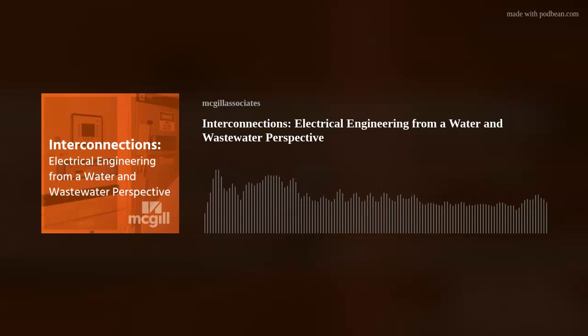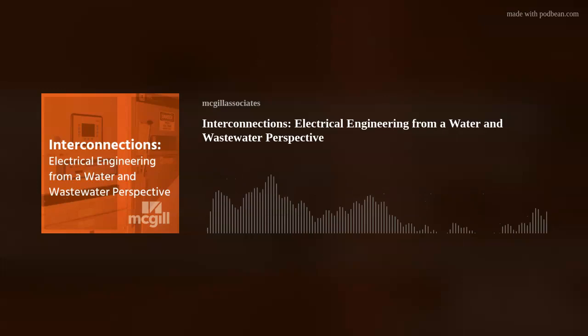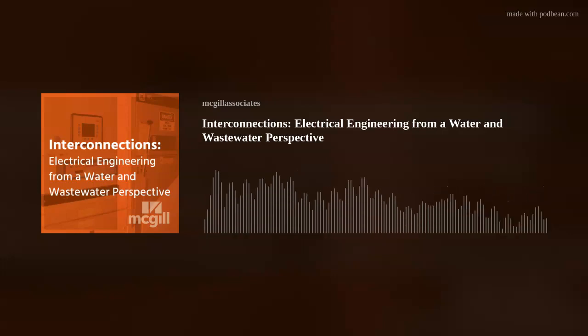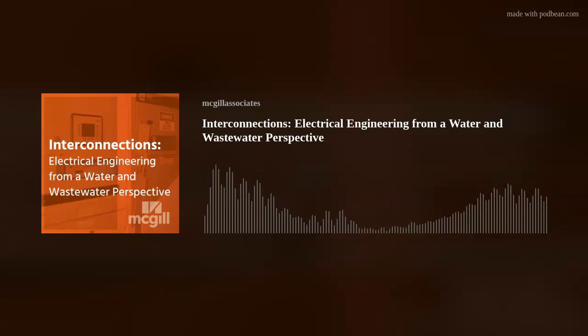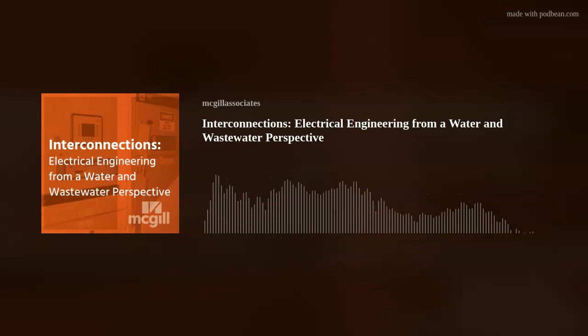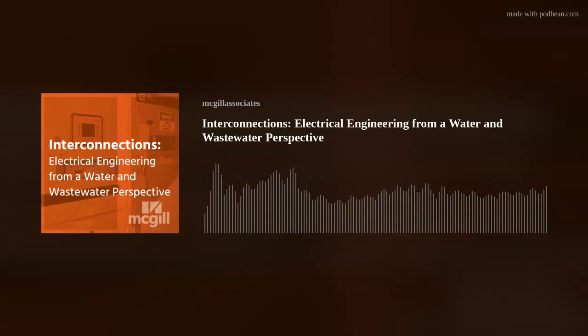And then with warnings and things like that, you might be able to see trends. Part of the SCADA system, you've got a historian in there, so you can watch and monitor certain things. You can monitor levels in tanks, you can monitor run hours on pumps. Am I having to run my pumps longer to get a certain height in the tank? Does that mean my impeller or my pump is getting bad or wearing out? Things like that you can catch through a modernized SCADA system.